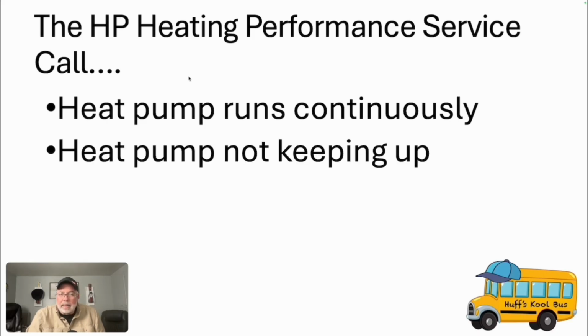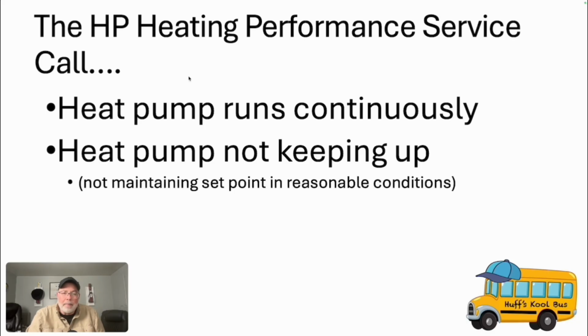Maybe the complaint comes in that the system's not keeping up and not maintaining a set point in reasonable conditions, where reasonable conditions means we're above the outdoor design temperature or something like that. So, of course, there could be many reasons for this. I've seen issues where people didn't connect the aux heater, and so the system wasn't keeping up when it got really cold out, because the heat pump alone was not enough to cover the load. Right? I've seen thermostat wiring issues. I've also seen issues that were just not sized correctly, things like that. Even though that may be the case, our approach to determine this is going to be the same. In other words, I approach it the same way regardless.